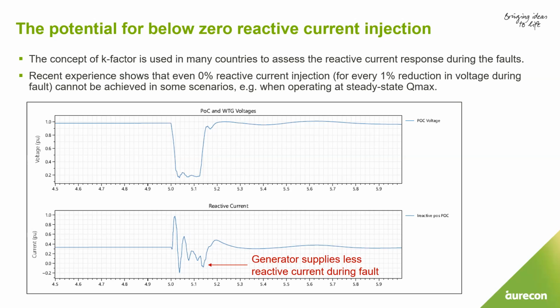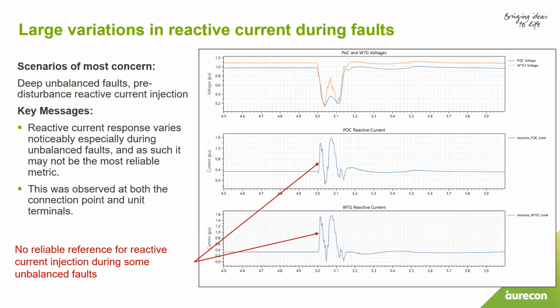What I wanted to highlight is exactly where I have put the arrow: just moments, a millisecond, before the fault clears, the reactive current injection is lower than when the fault initiated. That might cast doubt as to whether this particular IBR is providing a useful contribution, or any contribution, to the network. Is it perhaps even adversely impacting it? And if not, what else are we missing? Should we be looking at something else? Should we be changing the frame of reference perhaps? Let's see what else we learn.